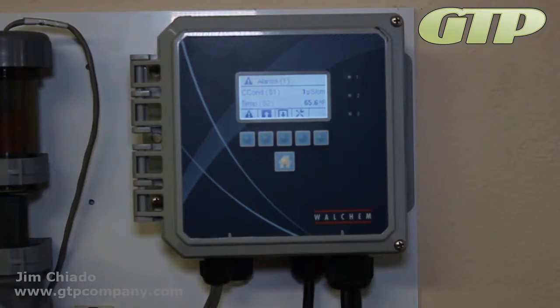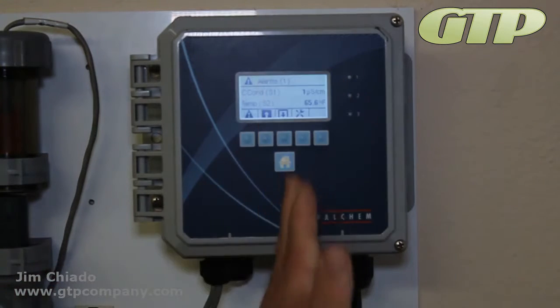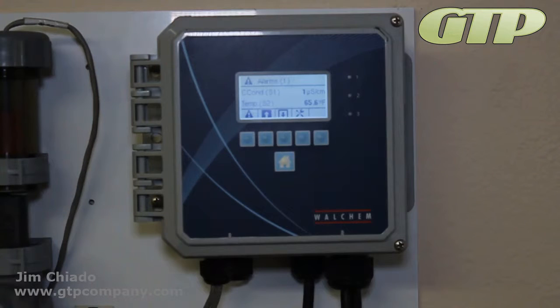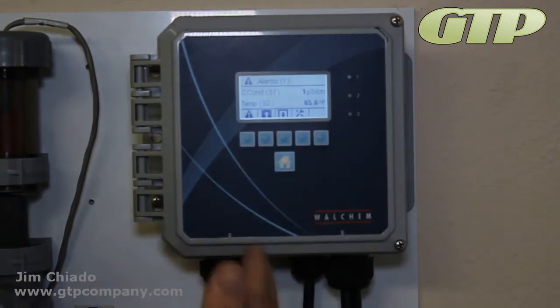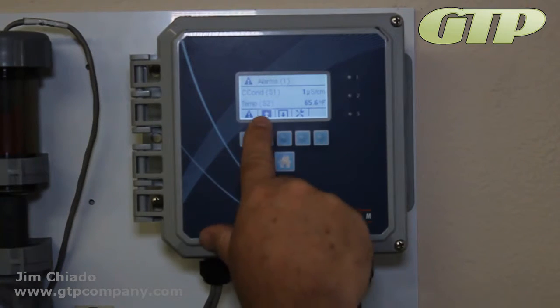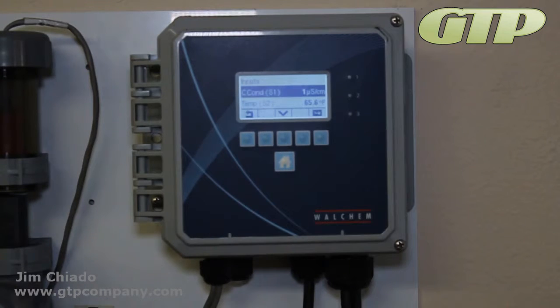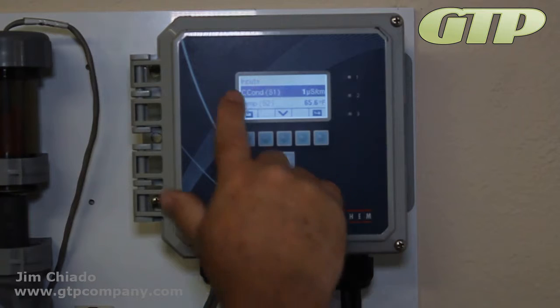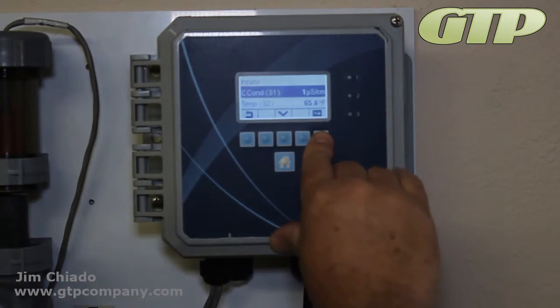Now, we're going to do the input parts of this. Remember, the machine has two different portions of it. There's the input side, everything headed into it, and the output side, everything going out. So I'm going to refer to it that way. You'll see that they're wired that way, as we understand. Inputs are the up arrow key. It's where our conductivity, temperature, our flow switch, and our flow meter are set. So we're going to go through the conductivity first.